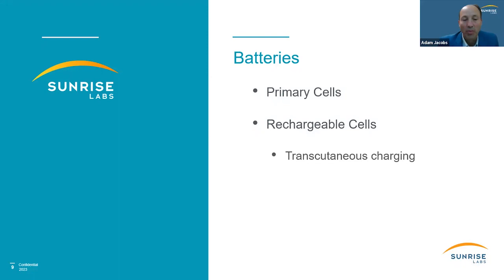So rechargeable batteries do provide higher power, but of course they require patient compliance and charging. There are different kinds of batteries. Some of them have higher density, some of them have higher instantaneous currents, and some of them have higher reliability, and you tend to trade those off for your application. For higher power applications like an LVAD, you would have very different requirements than a very low powered device. So that might be a place where you just don't have an option of recharging, and that might be why you would put an external pack, but not always.